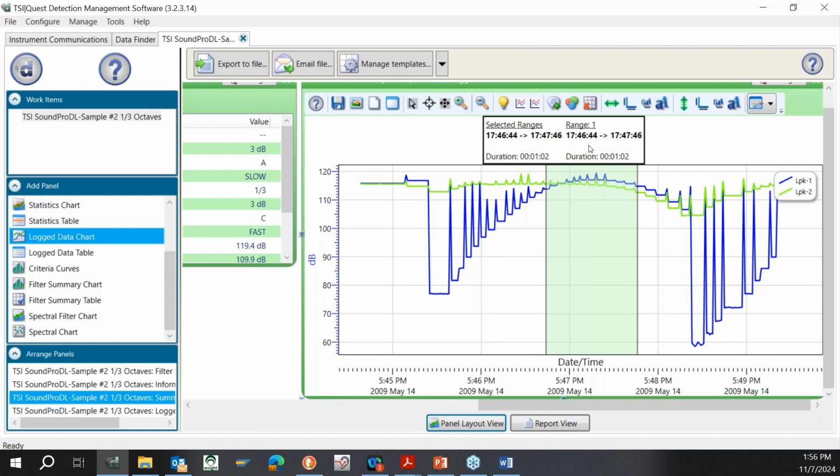If you take a gun range application, for example, because of the high peak levels, the microphone itself that is used in those applications is solely a Type 1 microphone, right? So it used to be called Class 1 in the standards. It was changed to Type 1, but it's accuracy and noise level that dictates the differences between the two, and application, right? But yeah, most people use Type 2, and that's completely fine, including OSHA.